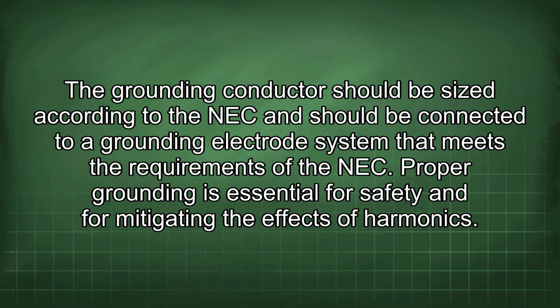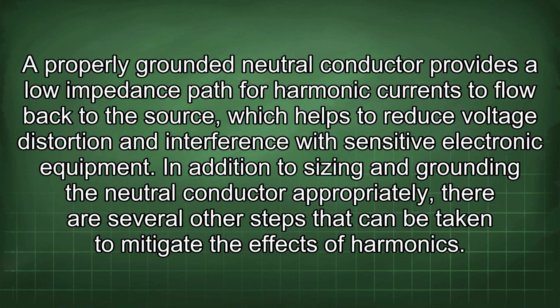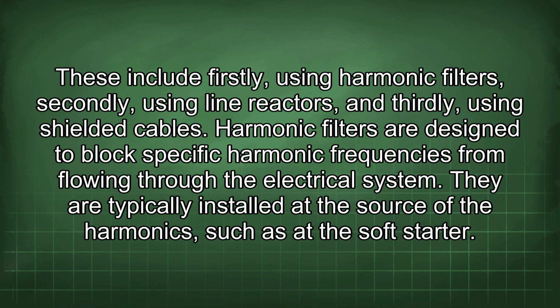Proper grounding is essential for safety and for mitigating the effects of harmonics. A properly grounded neutral conductor provides a low impedance path for harmonic currents to flow back to the source, which helps to reduce voltage distortion and interference with sensitive electronic equipment. In addition to sizing and grounding the neutral conductor appropriately, there are several other steps that can be taken to mitigate the effects of harmonics. These include, firstly, using harmonic filters, secondly, using line reactors, and thirdly, using shielded cables.